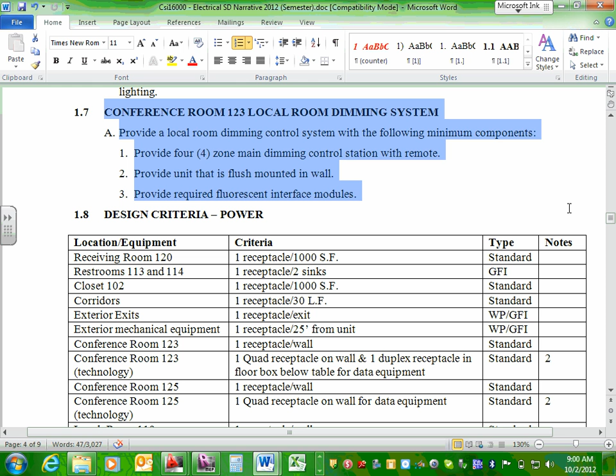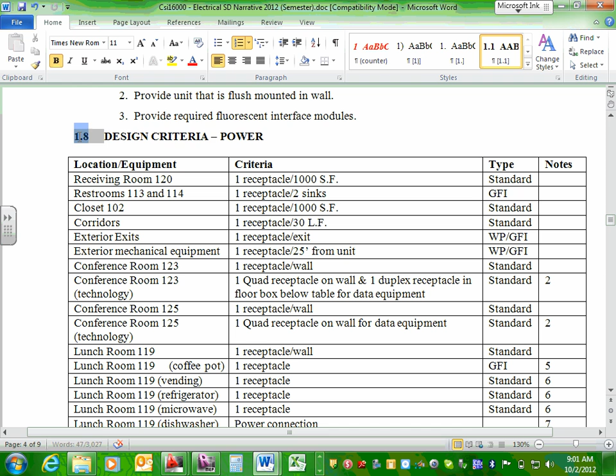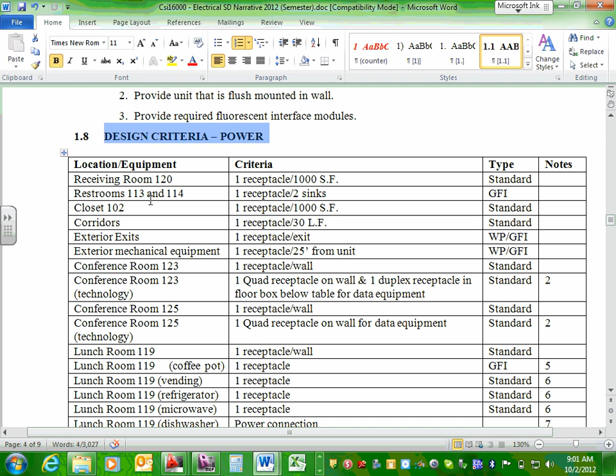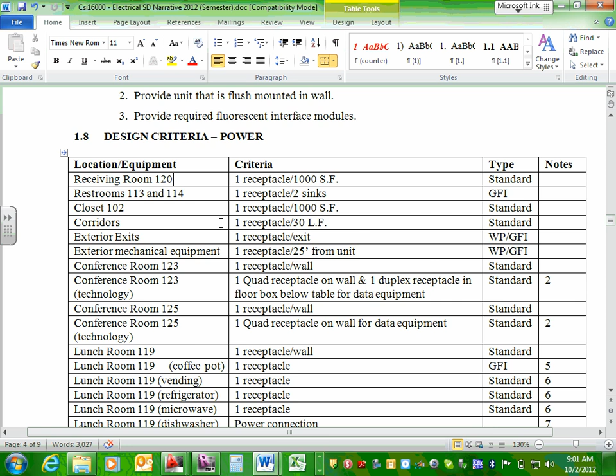On power: normally when you design a building you don't get information like this, but since we're an engineering firm, we're very specific about what we want in our building. When we meet with an owner at the start of a project, we don't get this—they don't hand us a spec saying 'in the receiving room I want one receptacle per 1,000 square feet.' They say 'I want a receiving room' and don't know what kind of power they'll need—they might need something, but they're not sure. So this lays out every single room, what we want for power receptacles in each space, and whether they're GFI, standard, or TVSS receptacles.